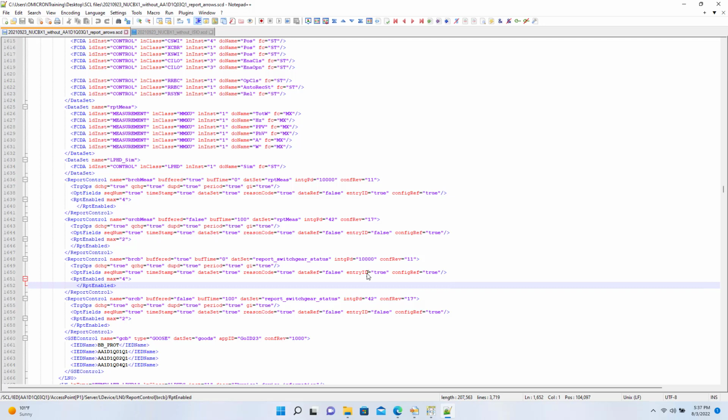And there are so many other recommended options. There are some system configuration tools and IED configuration tools from the manufacturers that also perform the comparison between SCL files, which is also highly recommended. In case you don't have access to those tools, we can use these open source, non-commercial freeware tools to find the difference between the SCL files.